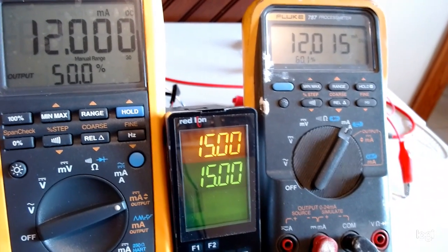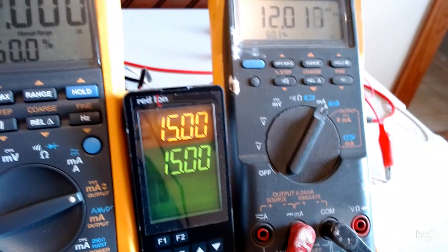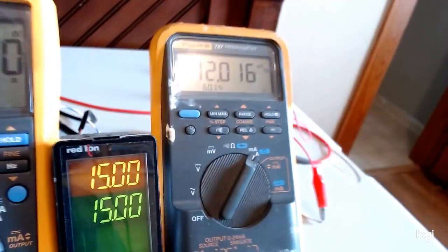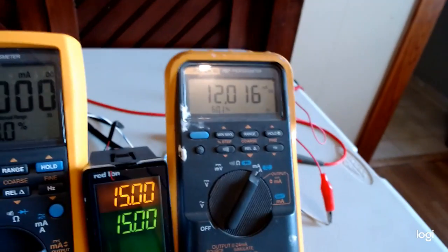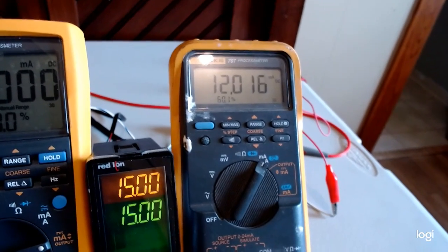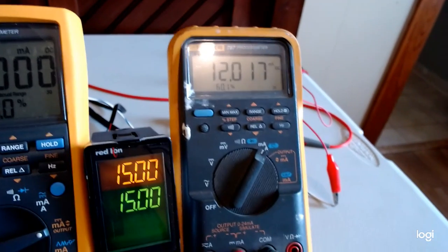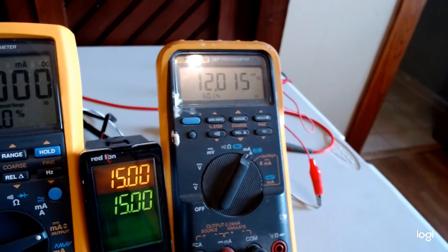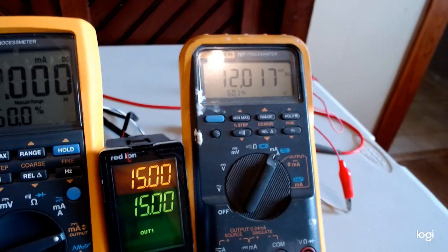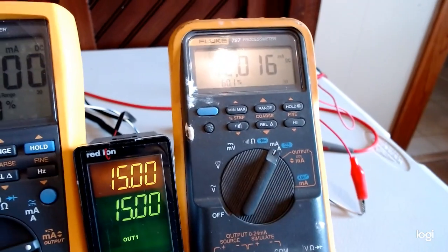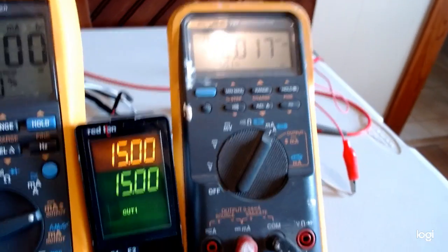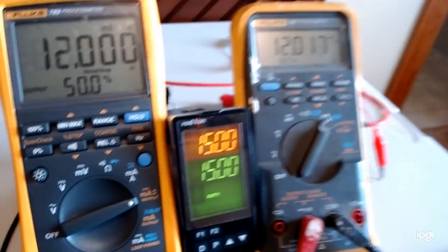Now, since we have no error, there's no difference between set point and process variable, then our output sits at 50%. Remember that formula, V sub O is equal to P sub G times the error plus 50%. There's no error to add to the 50%, so we're sitting at a 50% output. Now, when you look at this, you can see it's at 12.01, and like I said earlier, this is my knock-around meter, my own personal one, and it's probably off by 1/100th of a milliamp, okay? So we're not going to split hairs here.